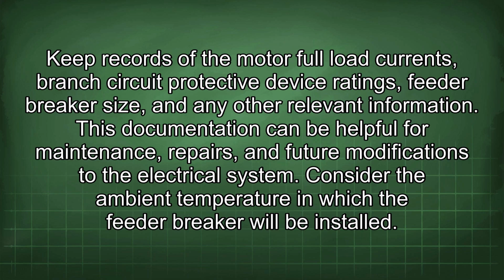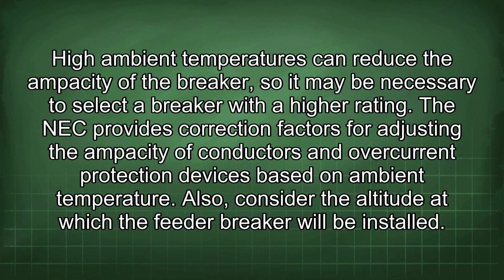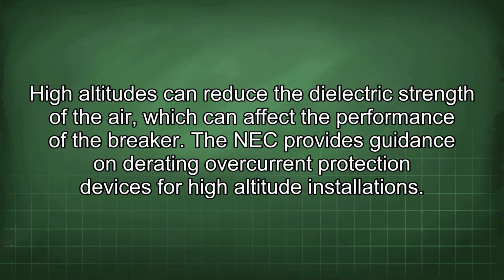Consider the ambient temperature in which the feeder breaker will be installed. High ambient temperatures can reduce the ampacity of the breaker, so it may be necessary to select a breaker with a higher rating. The NEC provides correction factors for adjusting the ampacity of conductors and overcurrent protection devices based on ambient temperature. Also, consider the altitude at which the feeder breaker will be installed. High altitudes can reduce the dielectric strength of the air, which can affect the performance of the breaker. The NEC provides guidance on derating overcurrent protection devices for high altitude installations.